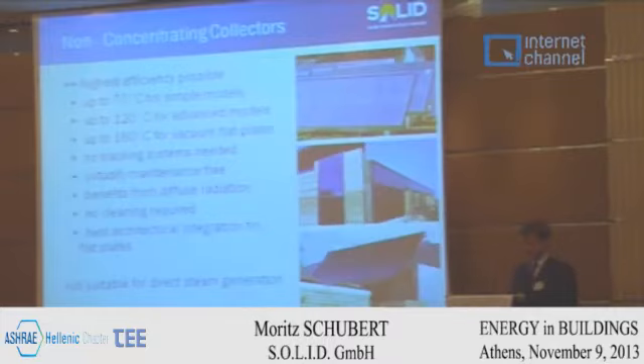Probably in order to reach high temperatures, high driving temperatures for absorption cooling machines, many use concentrating collectors which generate high pressurized water at 140 degrees or even steam. We do not. We go for an approach where we say we don't want to have these things where you need tracking, where you have moving parts, where you might need cleaning of the mirrors and so on, because it's all a big issue in maintenance. So we prefer to keep it simple and to use these flat plate collectors, which are quite highly developed at a high standard, but they are not as complex to operate as concentrating.